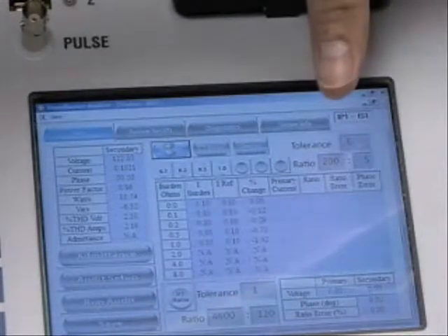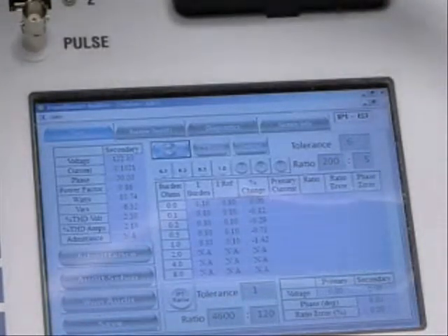The CT that I'm actually testing today is a 200/5 rated at 0.5 ohm burden. The tolerance I put in for this particular test is 0.6% because I'm not at full load of the actual CT at this time.